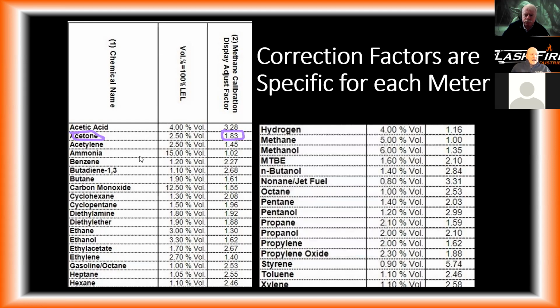So you can see acetone, something we've heard of. Acetylene, something we've heard of. Ammonia, something we've heard of. So as you go through this, you can see the common gases that we hear of. Propane, something we've heard of. And if you look at those correction factors, they're all less than 2. That's why I say if it's a gas that we're very aware of, just multiply it by 2. That's your safe factor there.